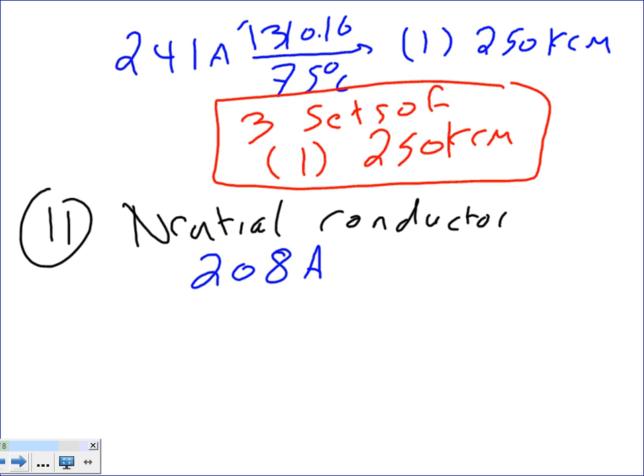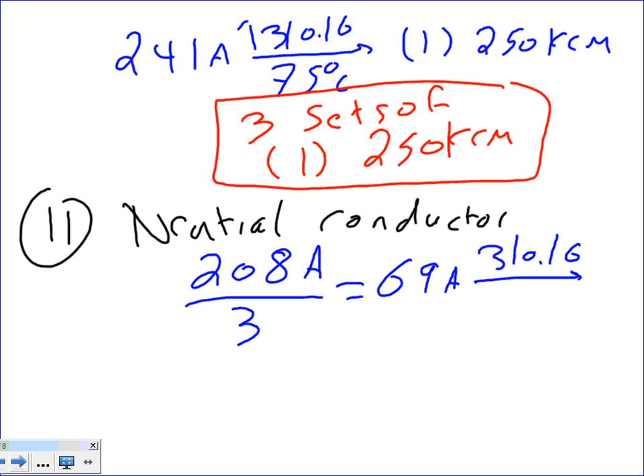So let's size this one first. If I want to size a neutral here, since we're paralleling, that's kind of an interesting situation. Divide this by 3. What do you get? 69 amps. Go to 310.16. Since it's a transformer, I know it's a smaller amp, guys, but all the lugs are most likely rated for 75, so just size it based on 75 degrees. What do you get? Number 4. I have one little problem, though.